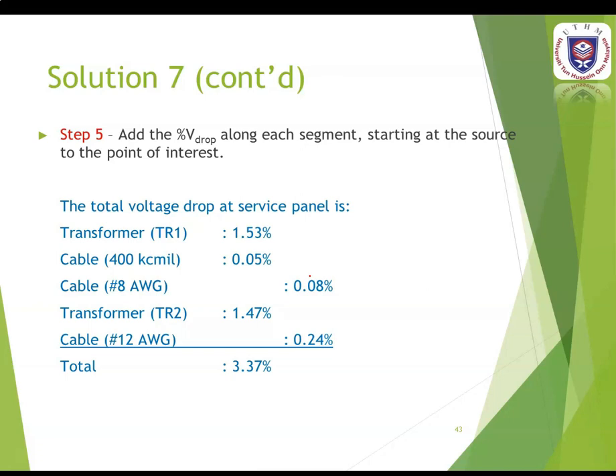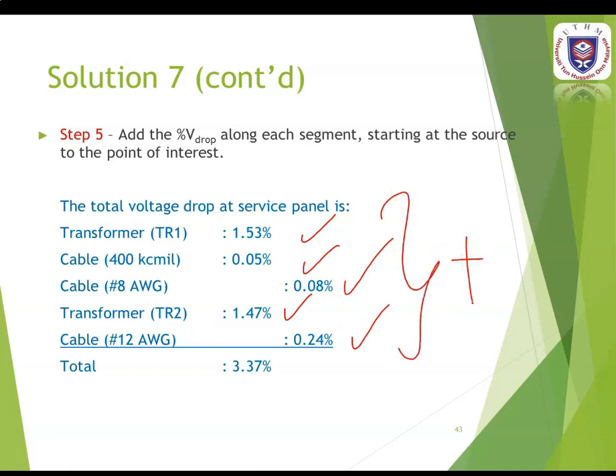The last step, same as single phase: sum all the percentages of voltage drop along each segment from source to load. Transformer TR1: 1.53%, cable 400 kcmil: 0.05%, cable 8 AWG: 0.08%, transformer TR2: 1.47%, cable 12 AWG: 0.24%. Sum all these to get the total voltage drop at the service panel for the three-phase system.